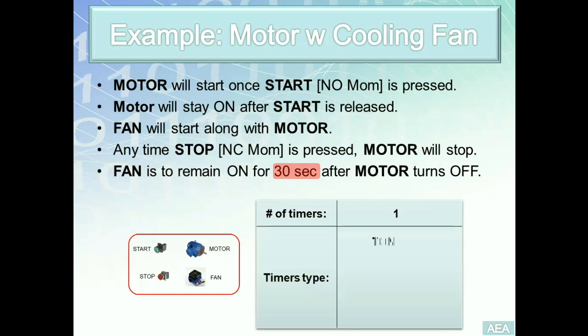The best timer to use out of the three — TON, TOF, or RTO — since we want the fan to be on for a certain time after a condition goes to OFF, the best and easiest approach is to go with an Off-Delay Timer (TOF). We can build the solution using TON or RTO, however it's easier and more straightforward using TOF. Let's see how this works in RSLogix.